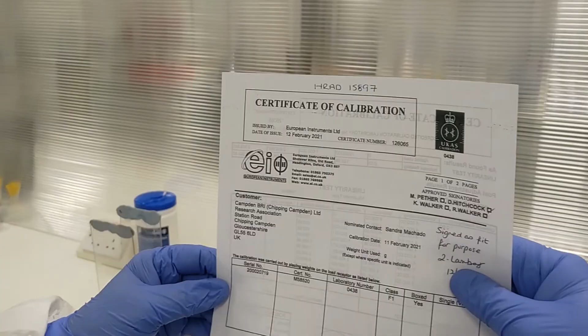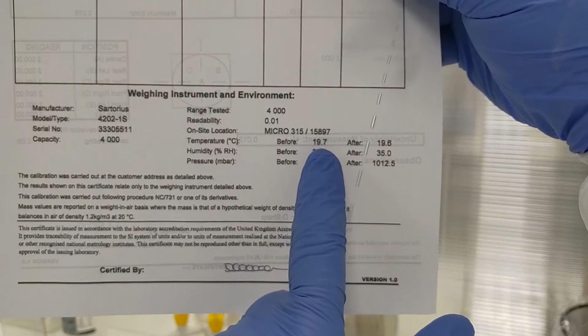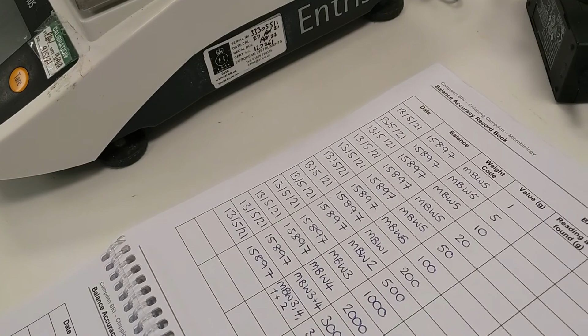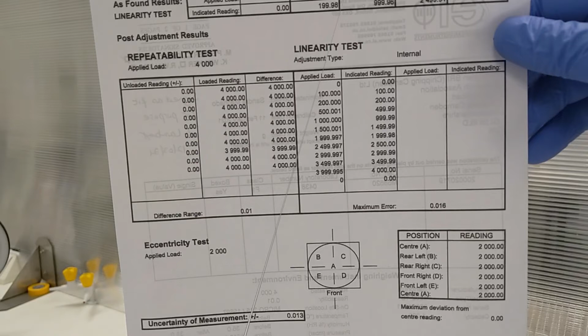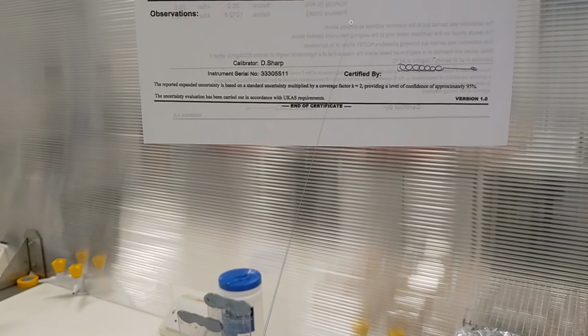15897. Let me just look at the device. Yeah, that's great. So it enables us to look at the content of the certificate. If you'd like to turn it over to the second page, we can actually look at the calibration information, make sure that the right repeatability, linearity checks, off-center loading checks were done, and that the results are within limits that are acceptable, and that the measurement of uncertainty is known.